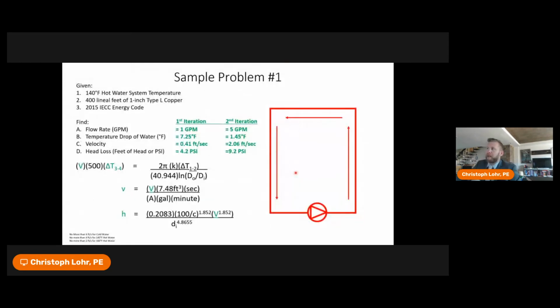All right, so let's say we had this system here that was all 1-inch type L copper. We had 400 lineal feet. We were utilizing a 2015 energy code, and we had a 140 degree Fahrenheit hot water system, right? So if we wanted to find the flow rate, the temperature, the velocity, and head loss, we'd have to make some kind of assumption of flow rate to begin with. So let's say we assumed 1 GPM was flowing through here in a steady state condition. Utilizing the series of calculations here, we'd end up with a 7.25 degree Fahrenheit temperature loss, a maximum velocity through that 1-inch type L copper of 0.41 feet per second, and a pressure drop of 4.2 PSI.